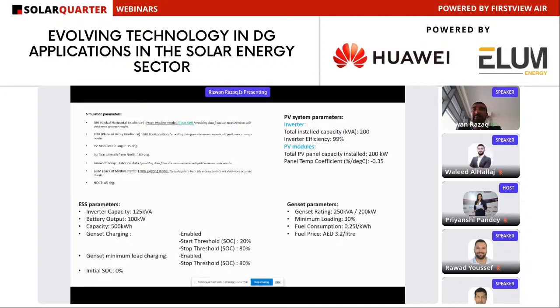Now, from a PV system perspective, what we've calculated here is around a 200 kilowatt system, with the PV modules around 200 kilowatts as well. From the genset perspective, we've got a rating of 250 kVA, around 200 kilowatts, with a minimum loading of around 30%, as this is an important factor to consider when calculating hybrid projects, as there needs to be a minimum load from the DG. So this will incur fuel costs and O&M costs as well. That is shown in terms of its consumption price, AED 3.2 per litre.